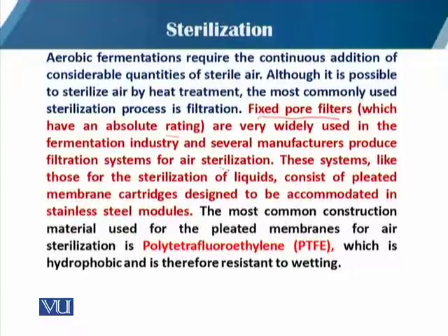These systems, like those for the sterilization of liquid, consist of pleated membrane cartridges designed to be accommodated in stainless steel modules. The most common construction material used for the pleated membrane for air sterilization is polytetrafluoroethylene, commonly known as PTFE. PTFE is hydrophobic and is therefore resistant to wetting, so the filter will not be wetted.